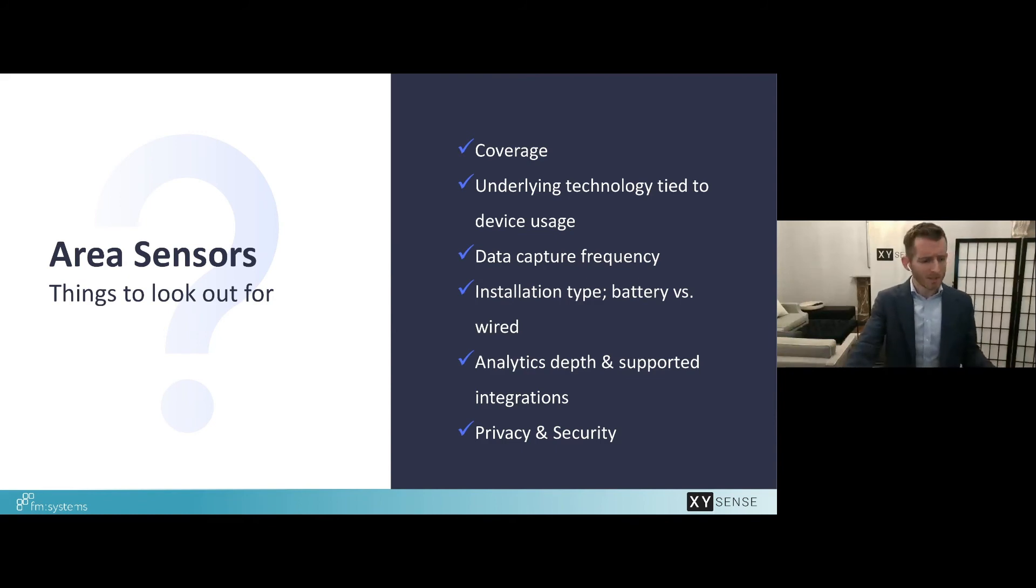So something to consider for battery-powered open area sensors is they actually drain their energy based on the number of people or traffic underneath. So they'll run out of energy or run out of battery at different times, which means you've got this logistics problem of having to swap batteries out. Also to consider is the sustainability aspect of batteries. A large deployment or a multinational could actually result in half a tonne to a tonne of battery waste every two to three years.